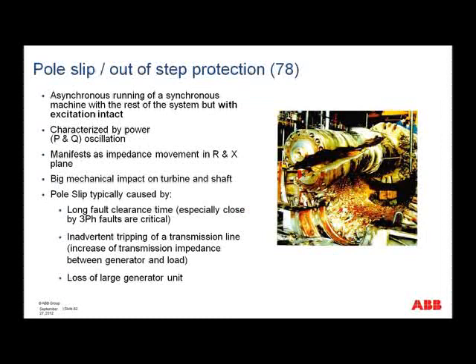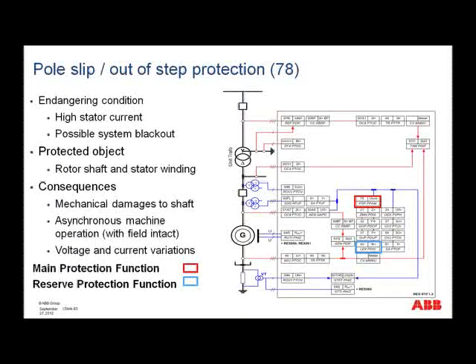Pole slip or out-of-step protection. Now remember, with the loss of excitation, we had the asynchronous running of a synchronous machine without excitation intact, but if we are talking about pole slip or out of step, then we have asynchronous running with excitation intact. It's characterized by power oscillation, P and Q, and manifests as impedance movement in the R and X plane. It has big mechanical impact on the turbine and shaft. It's typically caused by things like long fault clearance times, inadvertent tripping of transmission lines, etc. And here again, if you look at the protection picture, you'll see where we have the pole slip protection, and as a reserve function, maybe also we could have the loss of excitation.